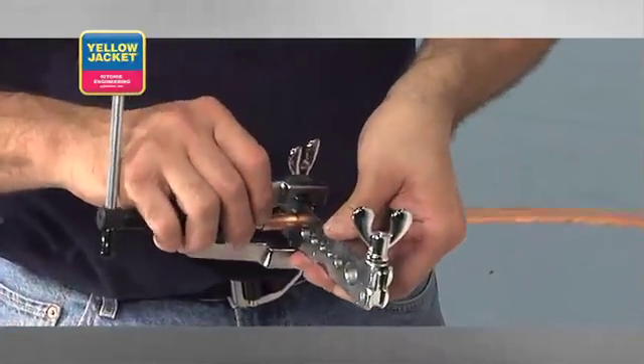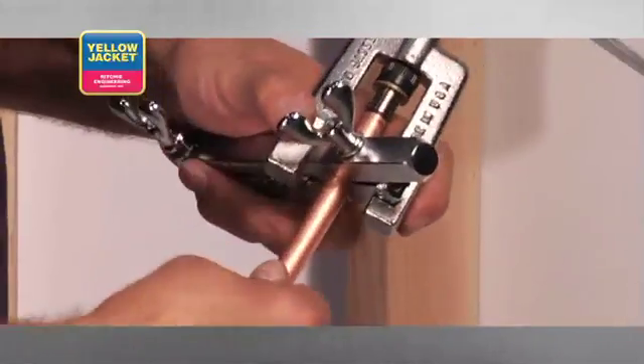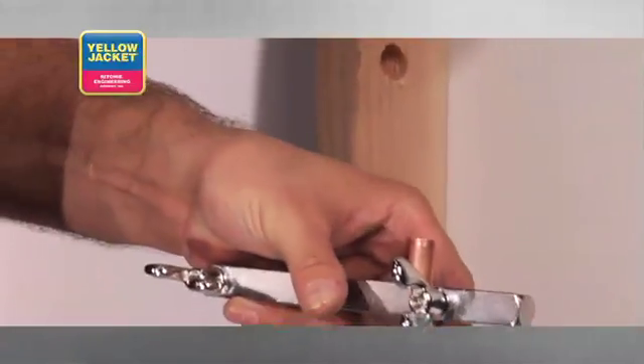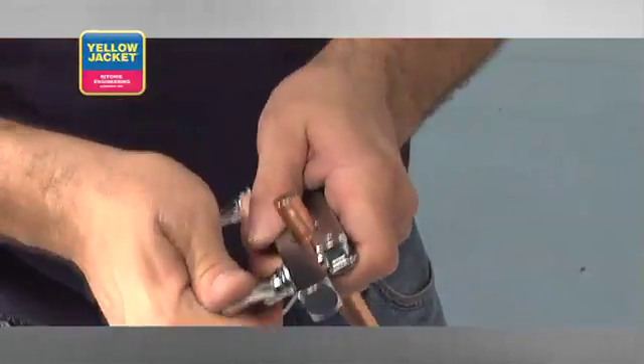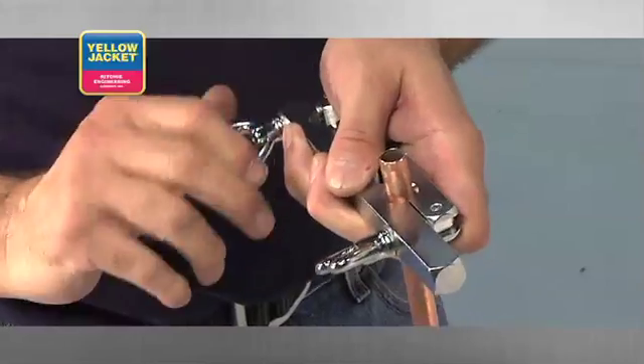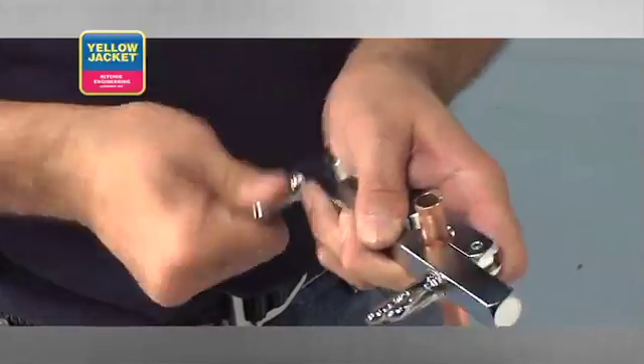Position the yoke and swage tip on the bar over the tube. Slide the tube up to the bottom. This is the position the bars need to be in before the butterfly nuts are tightened. Remove the yoke to prevent injury, and then tighten the bar starting with the butterfly nut closest to the tube. Tighten the second nut.